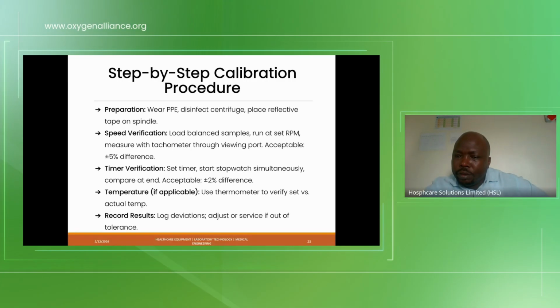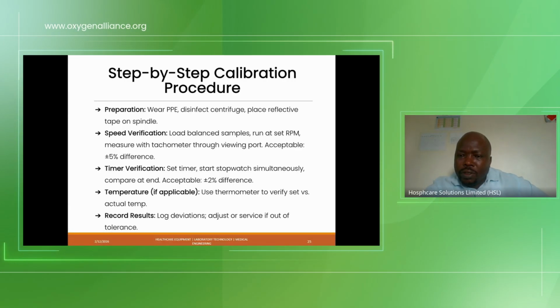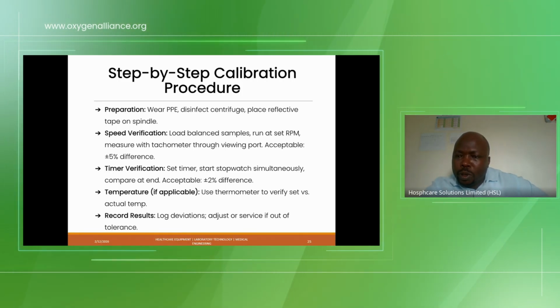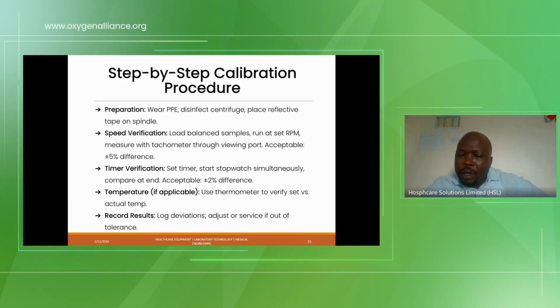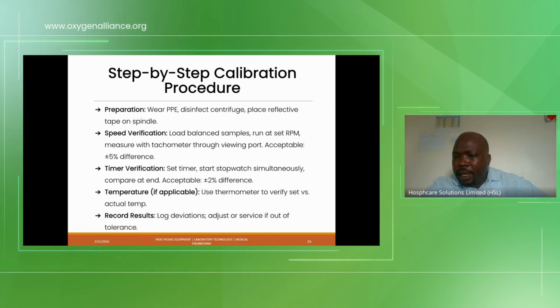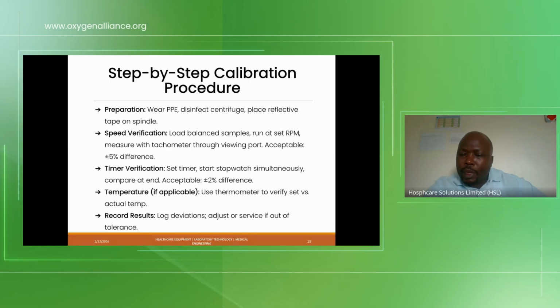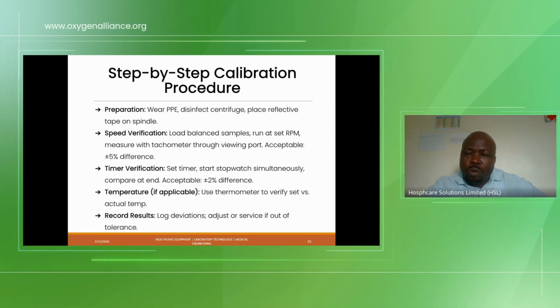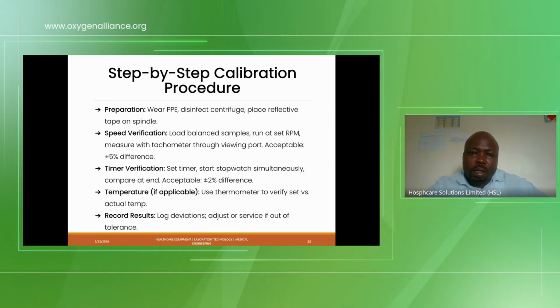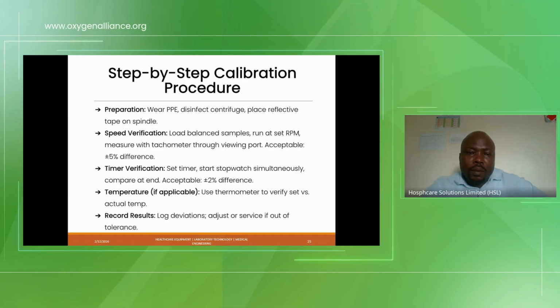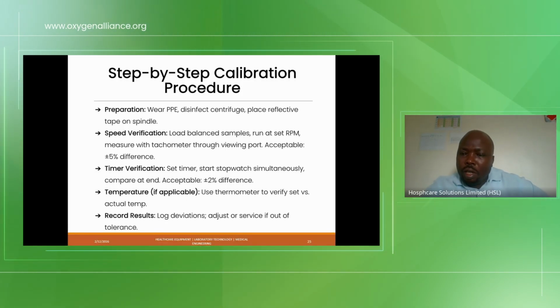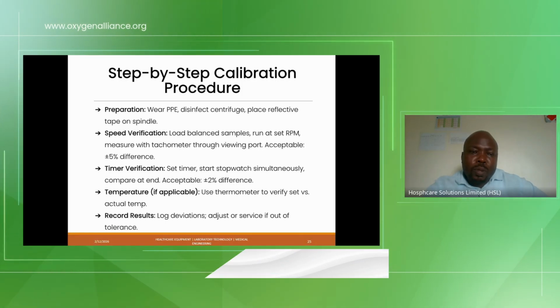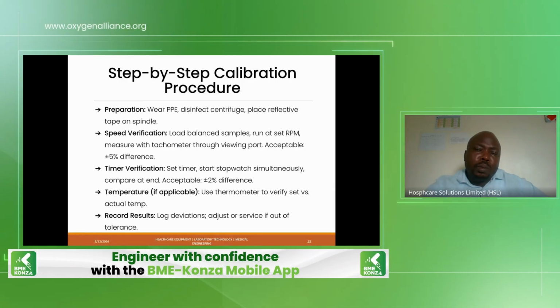Remember, every machine is designed or manufactured to hold a certain weight of samples. So once you overload it, you will put a lot of tension in the motor bearings. The force will be exceeded as per manufacturer guidelines. So if you want to use a sample with more weight, you'll be advised to do your machine selection keenly. For an industrial research centrifuge, you will require a bigger one. So you're supposed to check the data sheet.